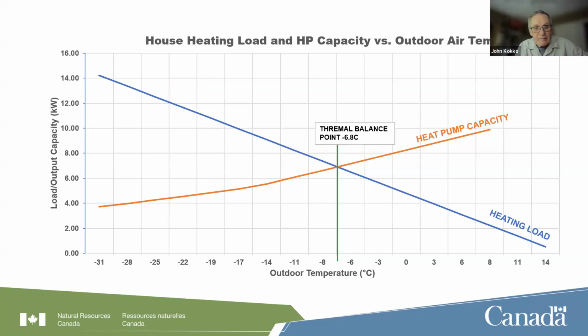One unfortunate issue with heat pumps is that the capacity does drop as the outdoor temperature drops. So while our heating load is increasing, the output from a heat pump is decreasing, which doesn't sound like a very good match. But at some point, there's what's called the thermal balance point or outdoor temperature balance point. In our example here, it's minus 6.8 or almost minus 7 degrees C. So below about minus 7, the heat output of the heat pump won't keep up with the load of the house, meaning the house is probably going to start cooling off a little more than we would like.